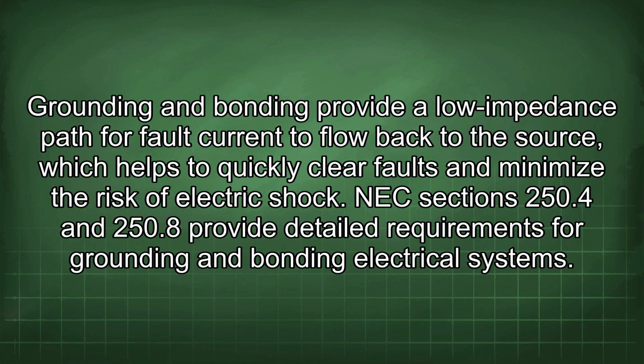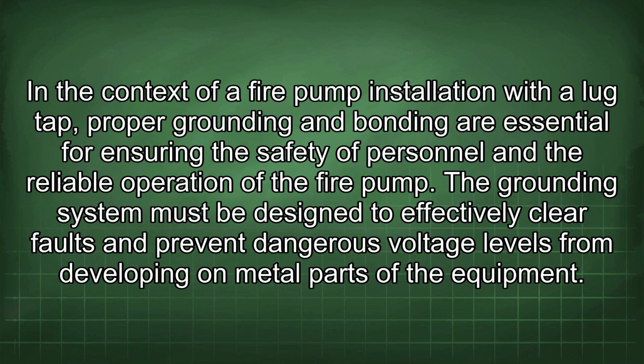Grounding and bonding provide a low impedance path for fault current to flow back to the source, which helps to quickly clear faults and minimize the risk of electric shock. NEC sections 250.4 and 250.8 provide detailed requirements for grounding and bonding electrical systems. In the context of a fire pump installation with a lug tap, proper grounding and bonding are essential for ensuring the safety of personnel and the reliable operation of the fire pump.